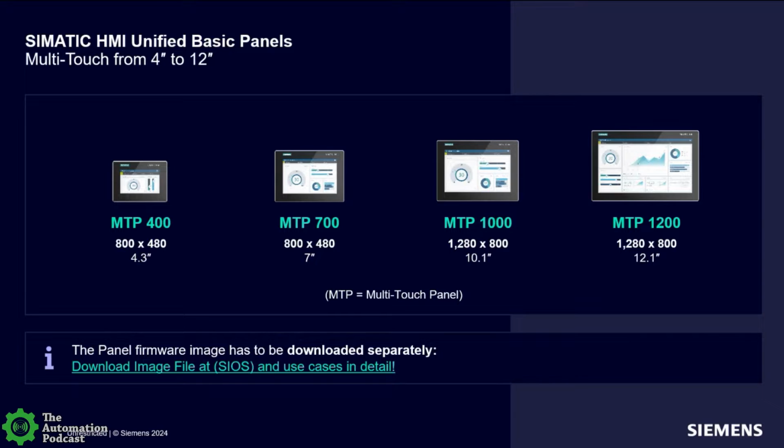So we help prevent you from putting something into an older image that isn't supported. But this allows us to support installations that have been running for years. If you had an installation at V18 and then you ordered a new replacement panel or a new unit this year and it comes from the factory with a version 19 image, when you download it, it'll just say, hey, you've got a newer image on this device, but that's okay. It can still handle this older image you've engineered to.